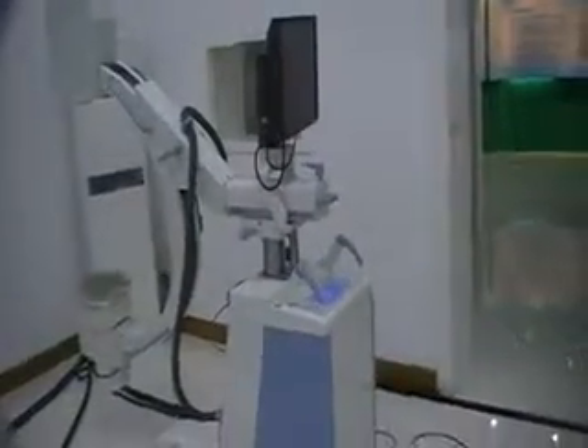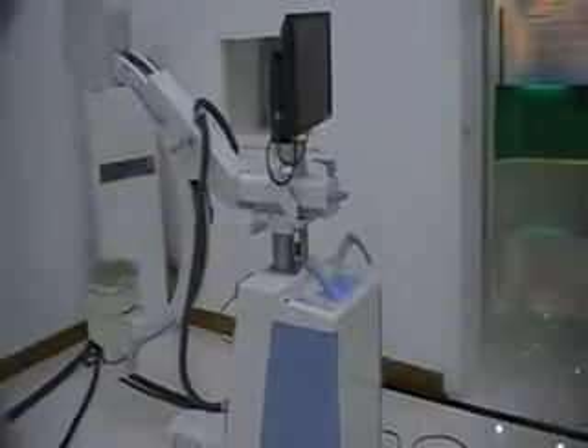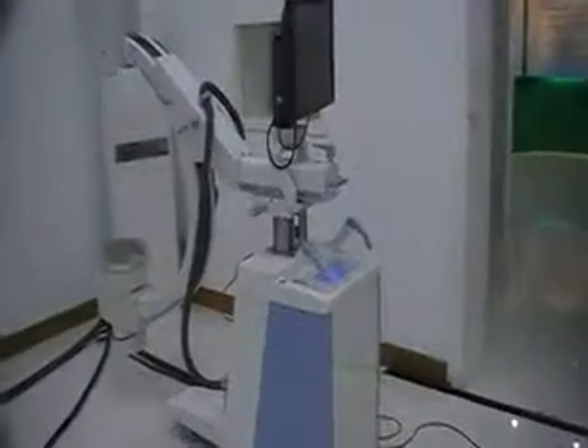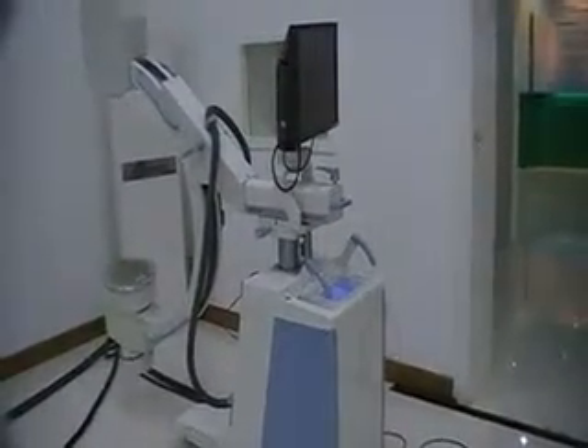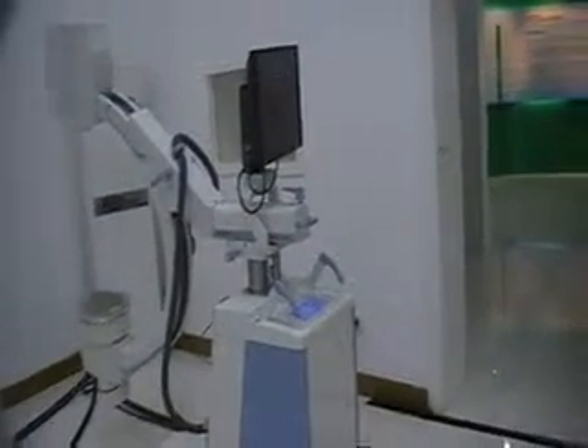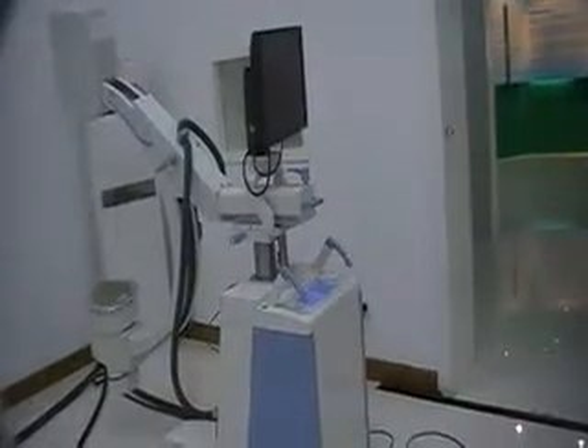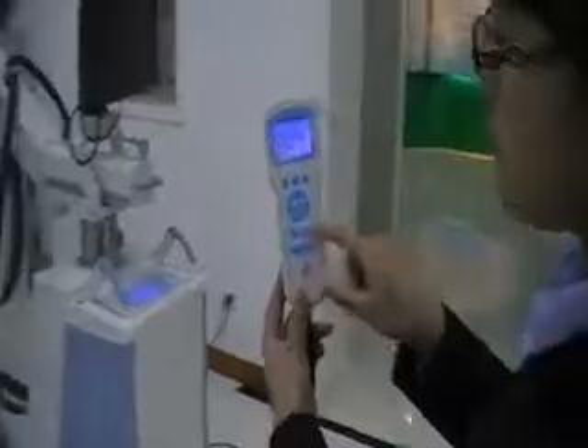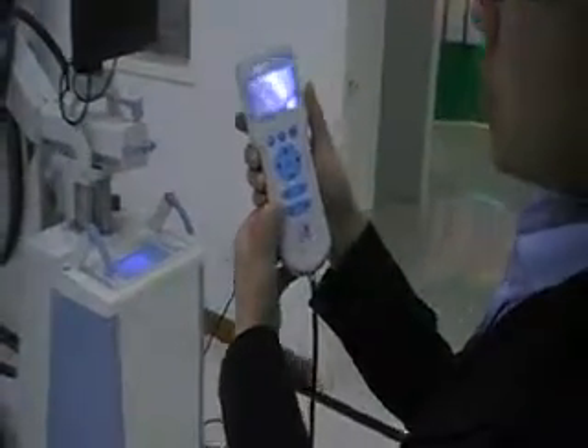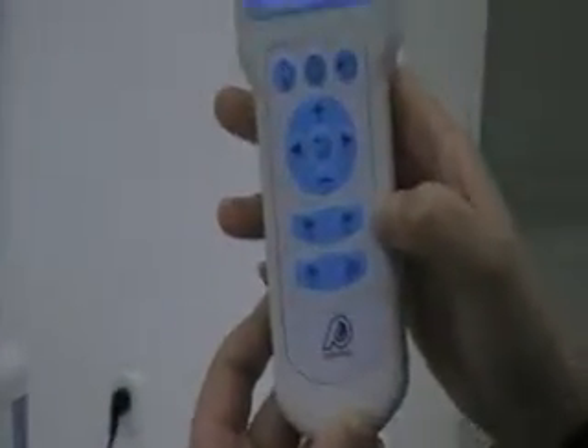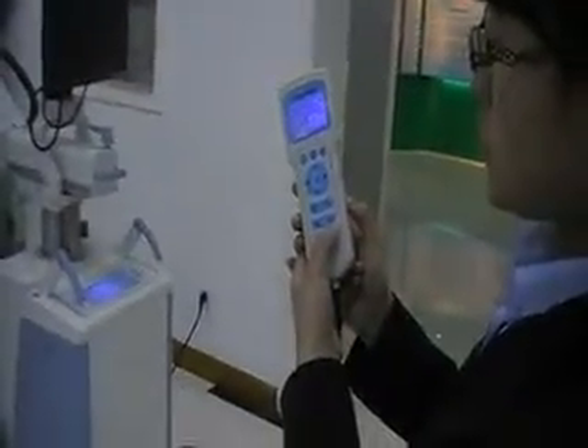So, let me just show you one movement with this. By pressing this button, and then pressing minus, it will go down. Then you press the plus button, then the C-arm goes upwards. So here we can see 4 symbols. The first one shows manual exposure, and the right one shows automatic exposure. This one shows pulse exposure. The pulse exposure distinguishes our PLX112C from the other PLX112 series. And the last one is to take a photograph.